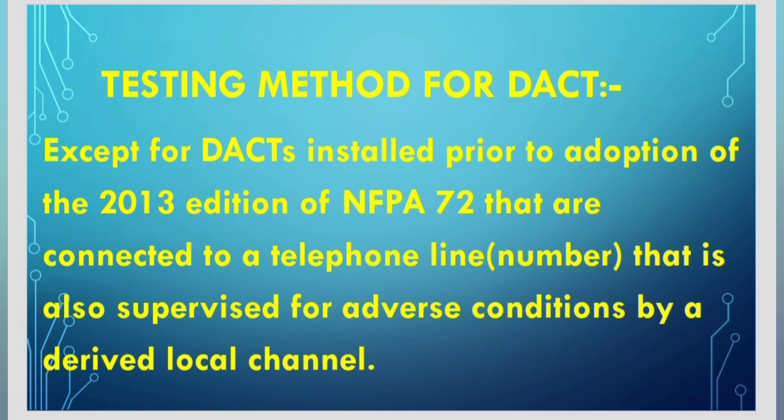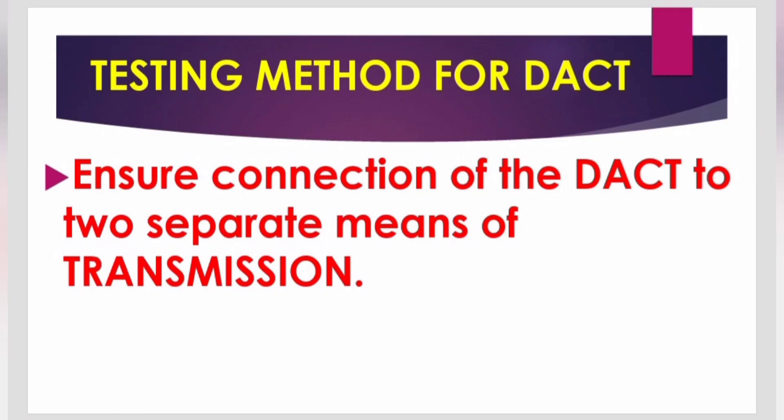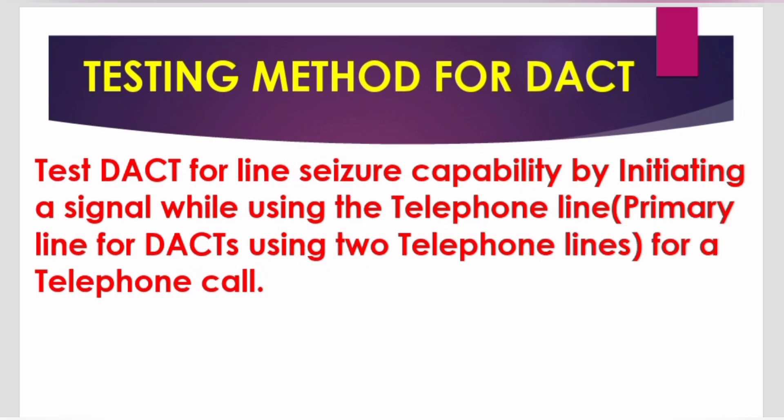This applies except for devices installed prior to adoption of the 2013 edition of NFPA 72 that are connected to a telephone line or number that is also supervised for adverse conditions. For a derived local channel, ensure connection of the DACT to two separate means of transmission and test the device for line seizure capability for initiating a signal.